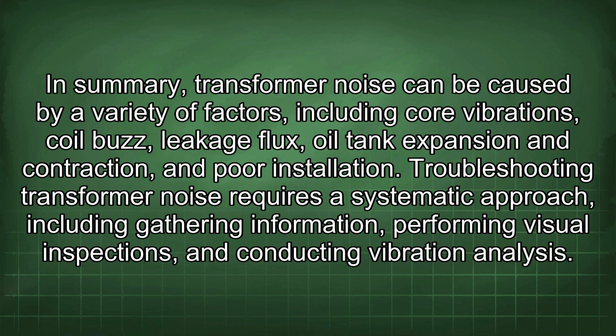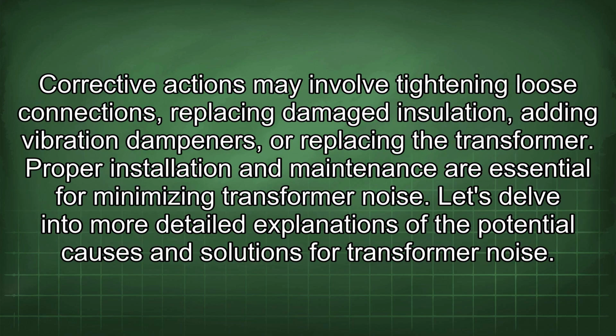Troubleshooting transformer noise requires a systematic approach, including gathering information, performing visual inspections, and conducting vibration analysis. Corrective actions may involve tightening loose connections, replacing damaged insulation, adding vibration dampeners, or replacing the transformer. Proper installation and maintenance are essential for minimizing transformer noise. Let's delve into more detailed explanations of the potential causes and solutions for transformer noise.